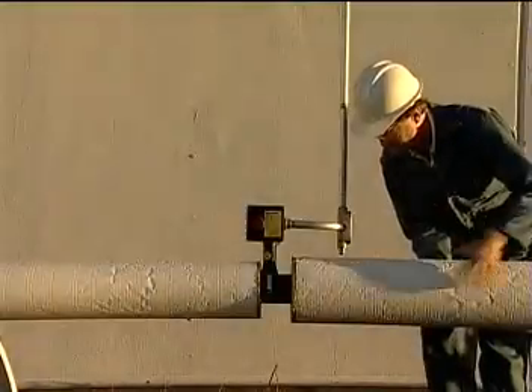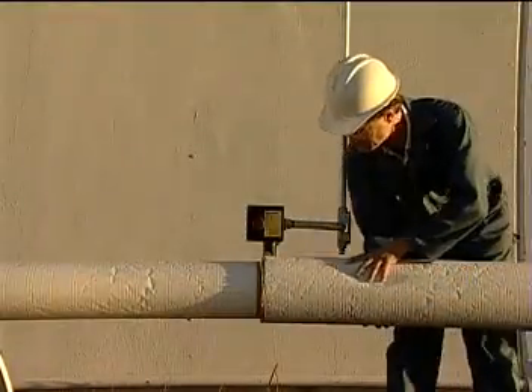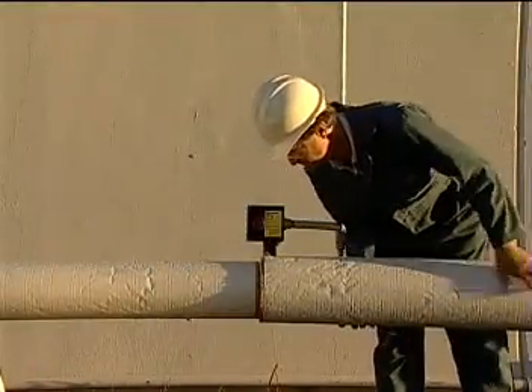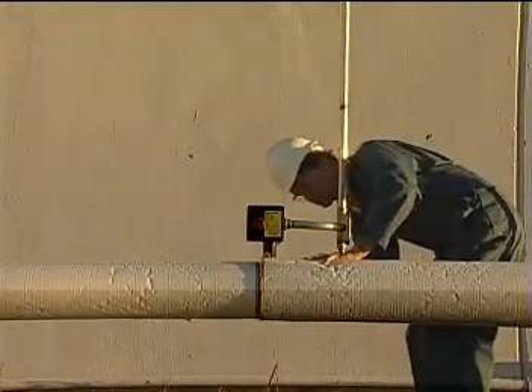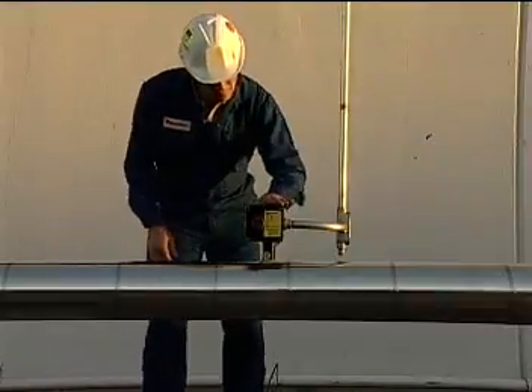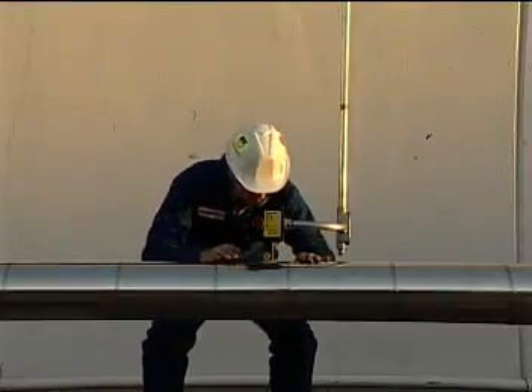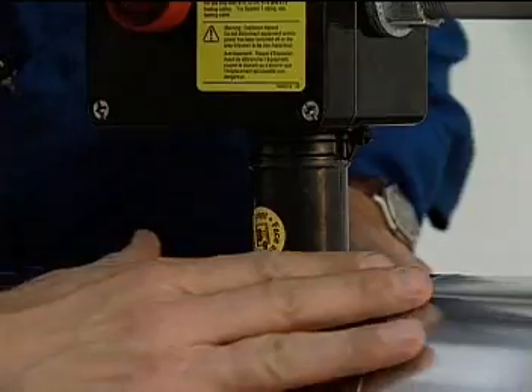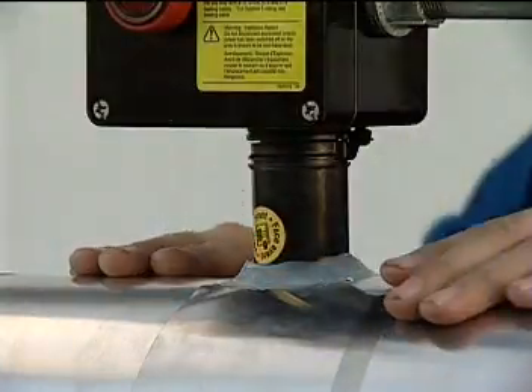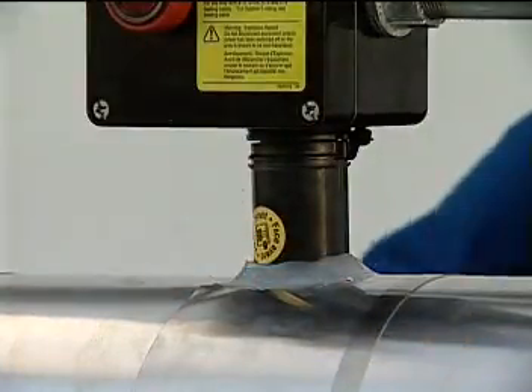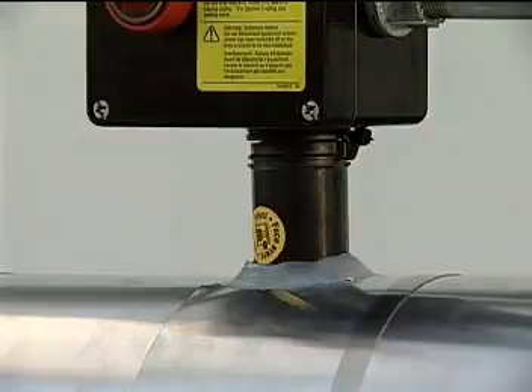Once the installation is complete and the system has undergone insulation resistance testing to make sure it hasn't been damaged, the thermal insulation should be immediately installed. Once the insulation is on, check that all valve stems, conduits, connection housings, tubes, and any other devices protruding through the insulation have been weatherproofed. This will protect the insulation from moisture, which could damage the insulation and render it useless.